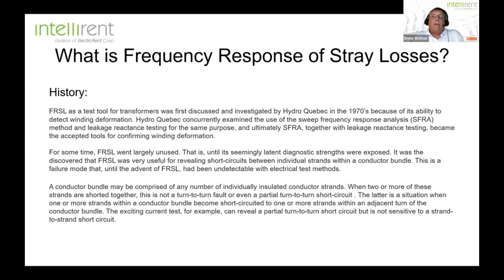So one of the key elements that we can do with your test set is that we have the ability to do what is called frequency response of stray losses. Now it's run exactly the same way as leakage reactance. What frequency response of stray losses is, is that Hydro-Quebec back in the 70s was looking for some additional tests they may use in addition to SFRA to see if they could find some conductive losses or some mechanical deformation.